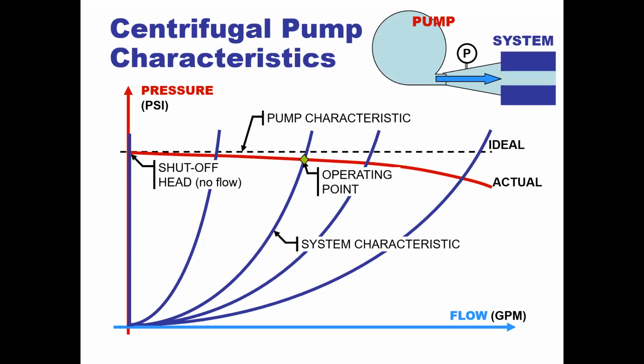Piping size, diameter. If we open up the piping size or open up the valve to a higher percentage open, we're not going to increase our pressure. Well, actually, our pressure will slowly decrease. Say again? You decrease your openness, so your operating point.